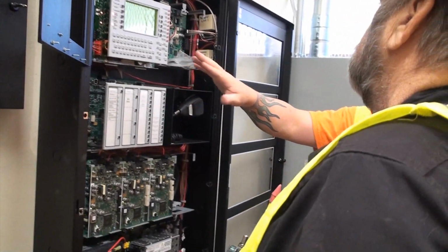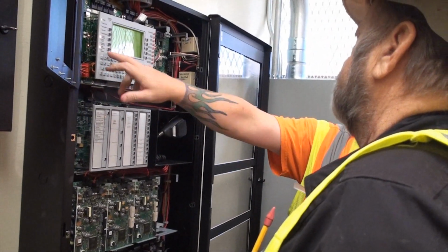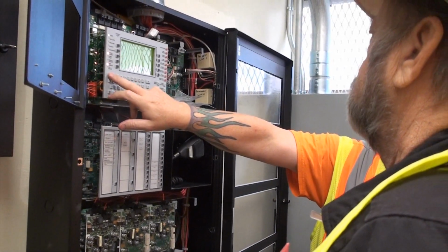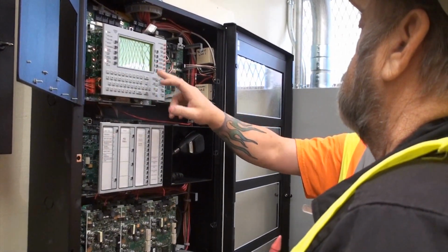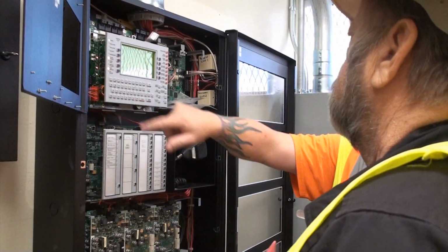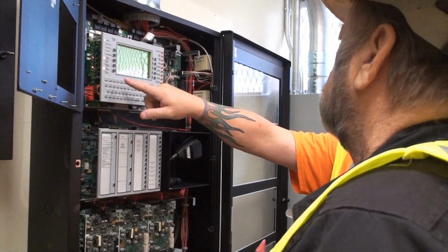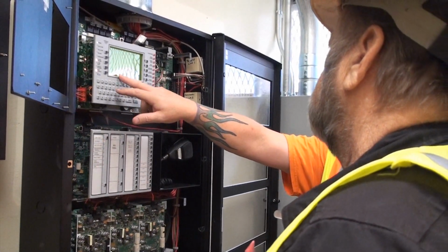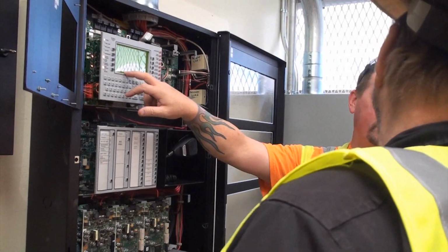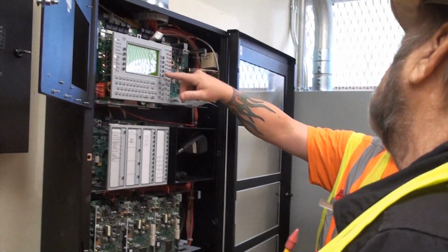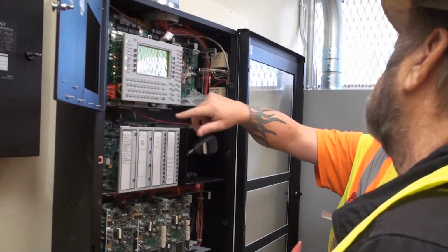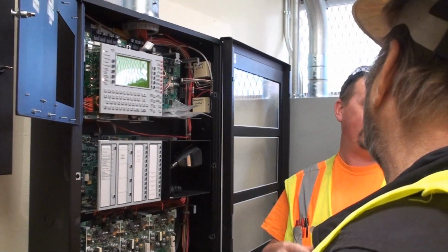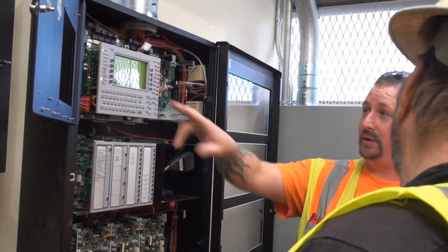So to be able to do any of that, you'll go to Program, and then to alter status, you'll hit just 8 ones, and then hit Accept, and then you get the Alter Status menu. And then you can disable, enable, check out the sensitivity, clear points, clear the history, your alarm history, trouble history. Put it on walk test, change your time and date, and then you also have a control on and off. So if you want to activate a relay without actually hitting the smoke, you can put that.